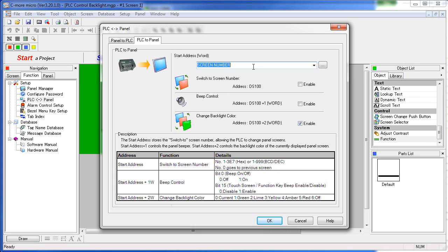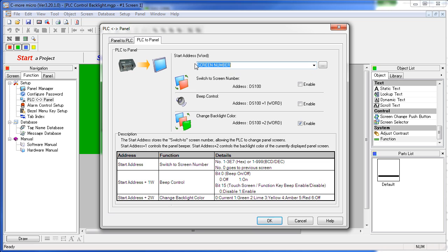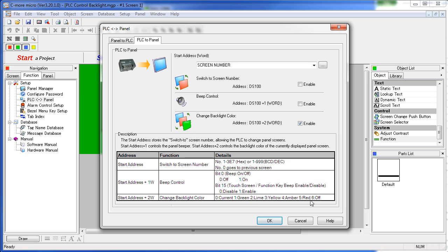Now we want to configure the PLC to Panel control of the backlight color. To do that we need to set up a tag where the PLC can put the screen number. The C-more Micro then looks at that tag which is at address DS100 plus 2 for the backlight color if this checkbox is enabled. Note that there is a little reference sheet down here telling you that at this address it will change the backlight color and here are the colors. Again 6 being off, 0 being the screen color that was originally programmed.